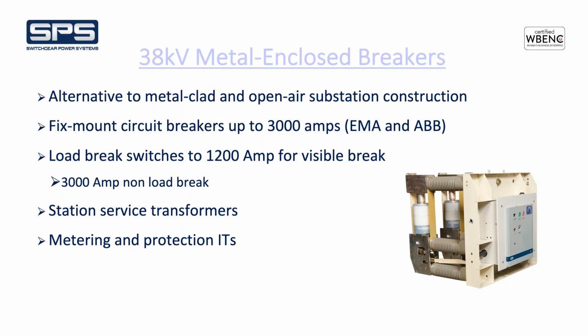Load break switches up to 1200 amp, and that is how we provide visible break. Obviously, with the breaker not being draw out, there needs to be another means of visible break. And we do offer up to 3000 amp for non-load break switches. And even on a load break switch, a typical switching operation would not be done under load. You would use the circuit breaker. You would open the circuit breaker prior to opening the switch. And then we incorporate the station service transformer, any instrument transformers that you need, as well as protection and control, obviously.